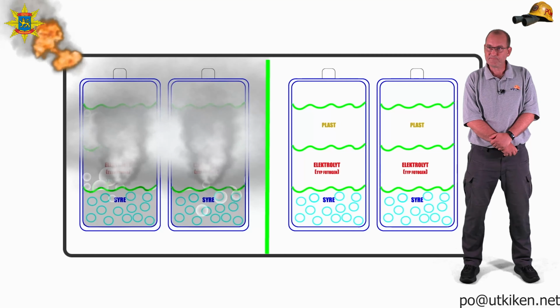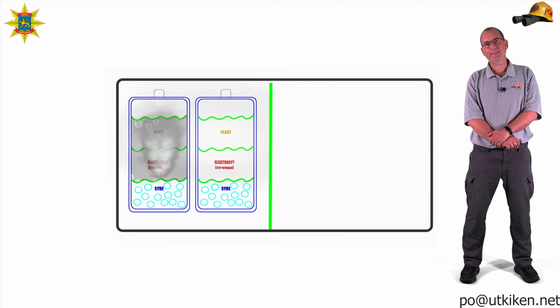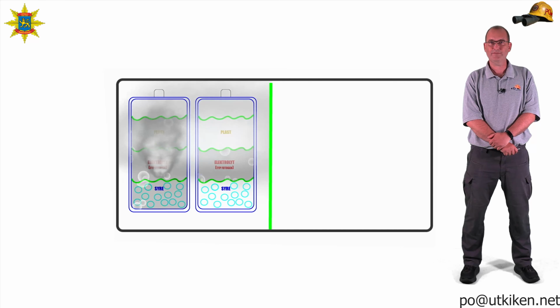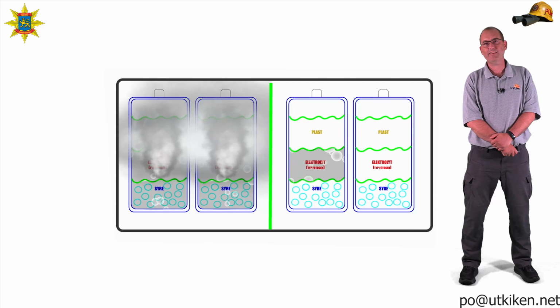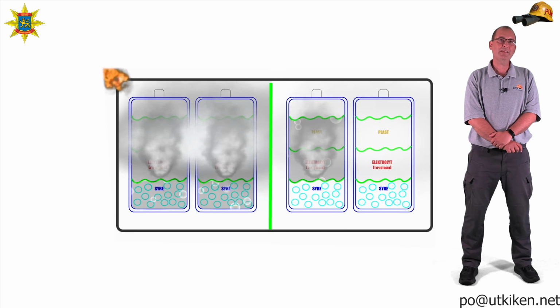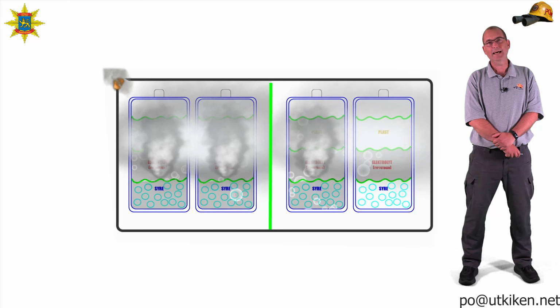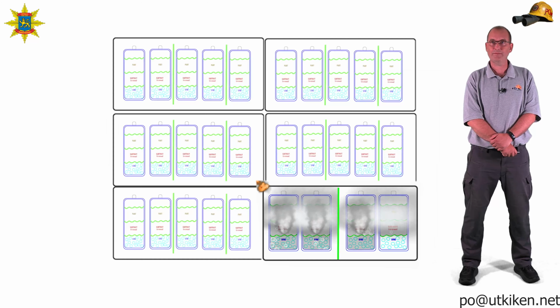The next thing happening when we have that much heat is that the chemically bonded oxygen starts to release from where it was bonded. It is in oxides in the battery. The oxygen is delivered to the fire and creates even more heat from that thermal runaway. And in that way it will spread to more battery cells.